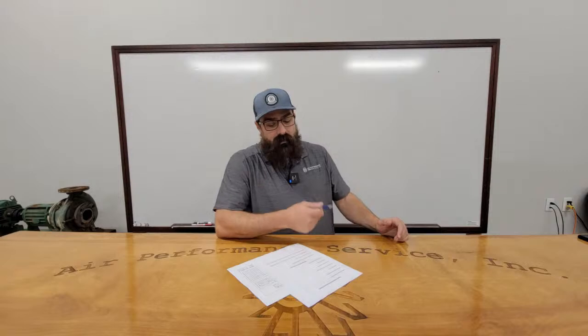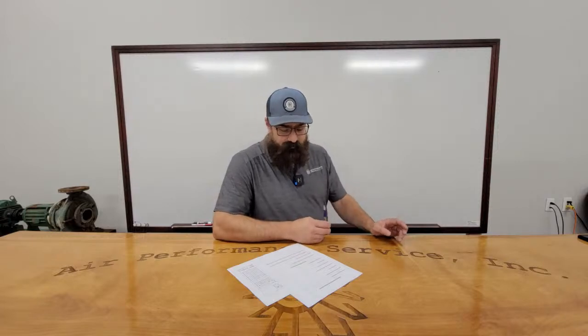So yeah, the key with the water source heat pumps on our side is making sure you have flow established before you would call for a compressor, because if not, you'll go out on high head. You can run them for a short amount of time, but a lot of them will trip. On building automation systems, sometimes they have ISO valves, sometimes they don't. It just really depends. Most small water source heat pumps, you're not going to have an ISO valve. But then again, you get some bigger ones, and they do. But we'll touch on scuds in a little bit.